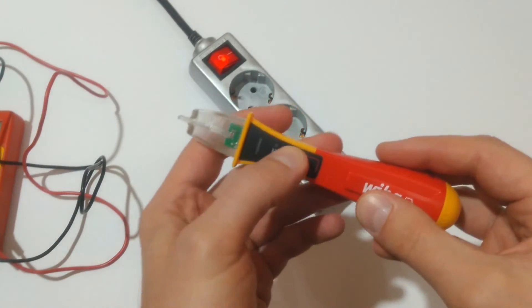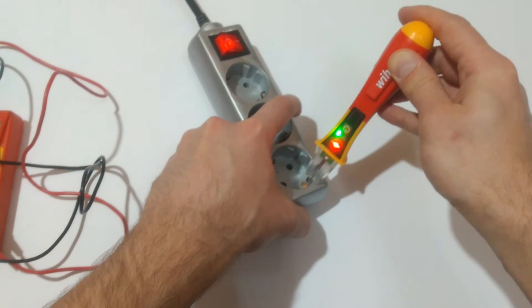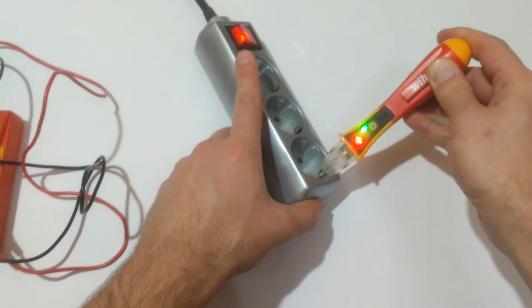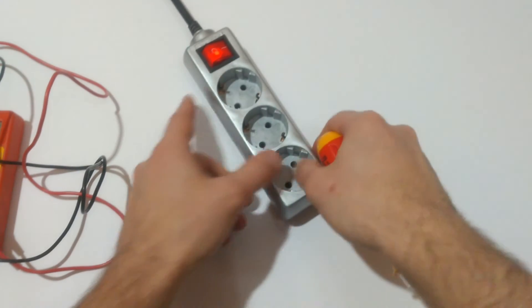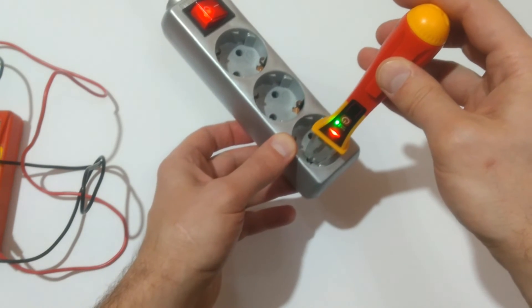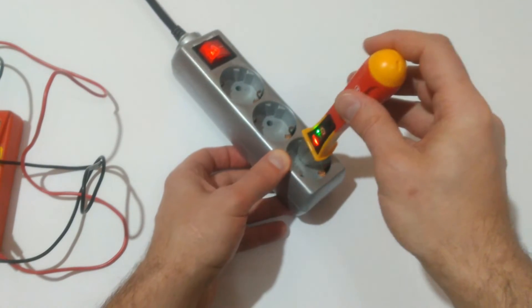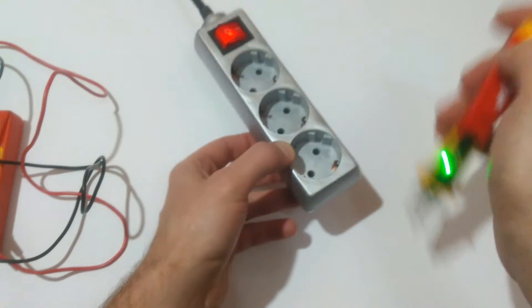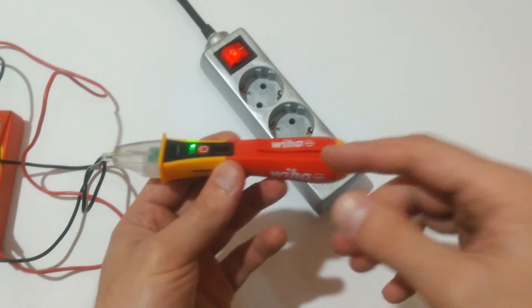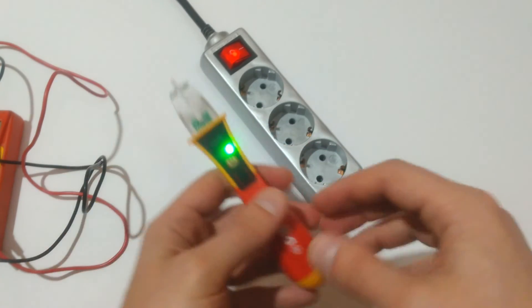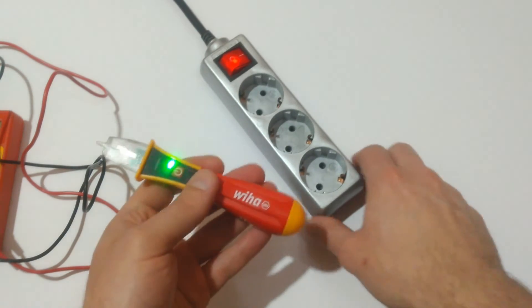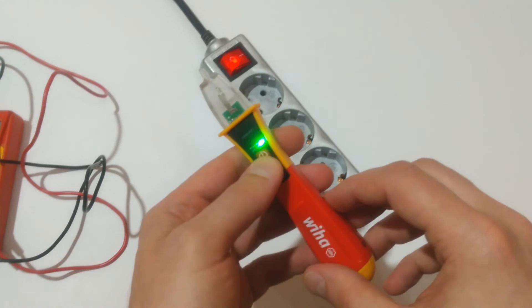Continuing with Wiha. And here we have some indication for live conductor, also live conductor on the neutral, and again a red light on the live. So in this situation the Wiha is not the best choice, it will mislead you. Indeed there is a problem with the power strip but with the Wiha you might get the wrong impression.